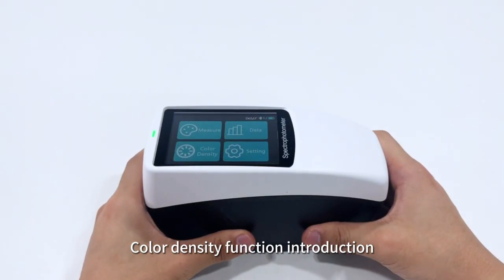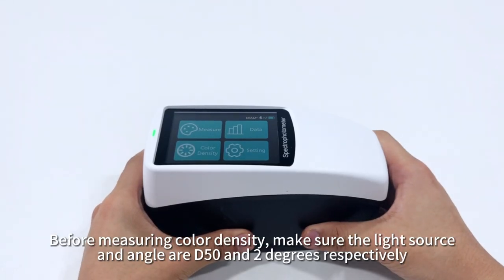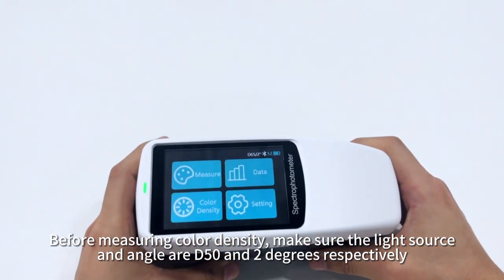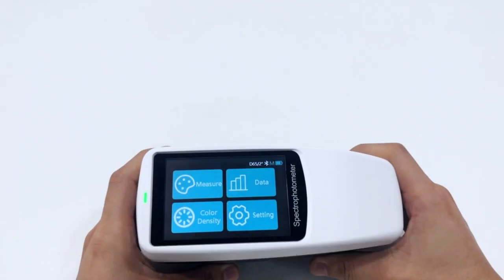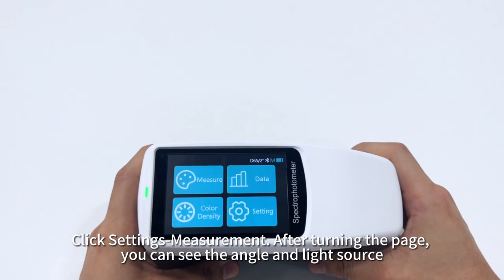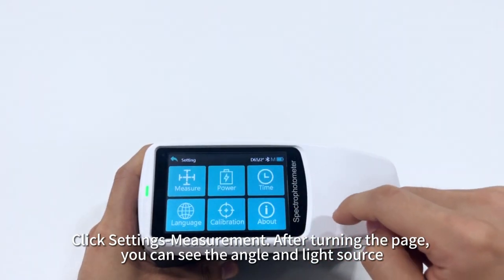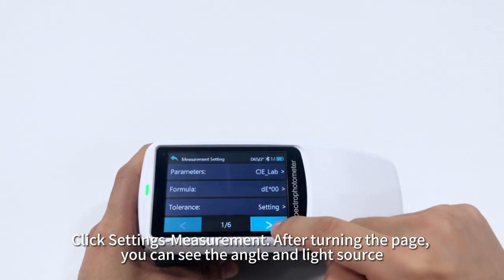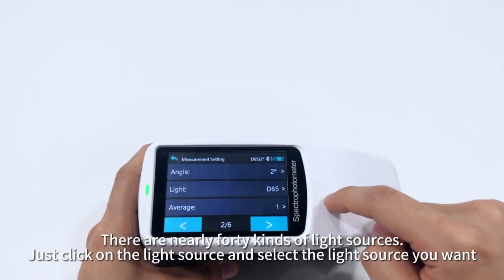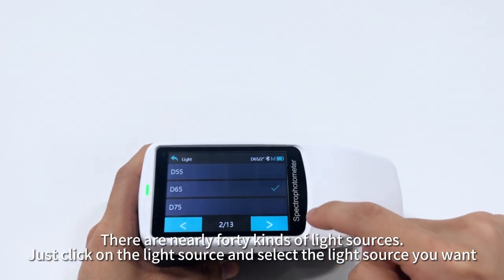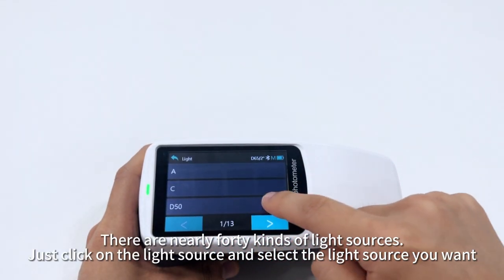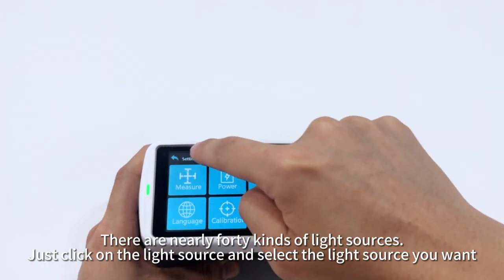Color density function introduction. Before measuring color density, make sure the light source and angle are D50 and 2 degrees respectively. Click Settings, Measurement. After turning the page, you can see the angle and light source. Click to switch angles. There are nearly 40 kinds of light sources. Just click on the light source and select the light source you want.